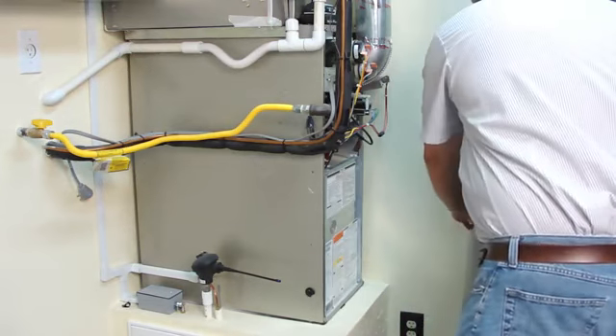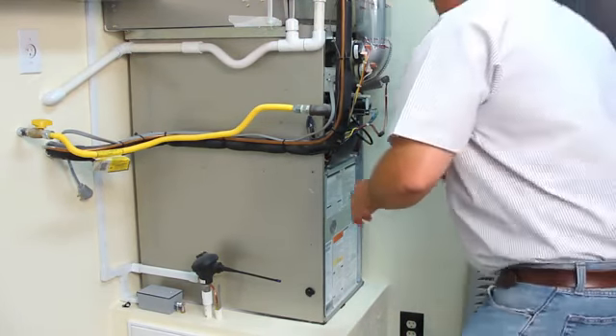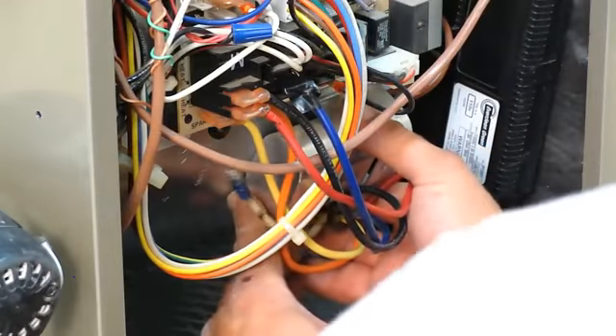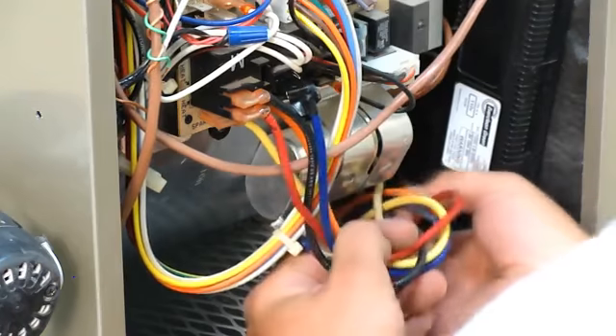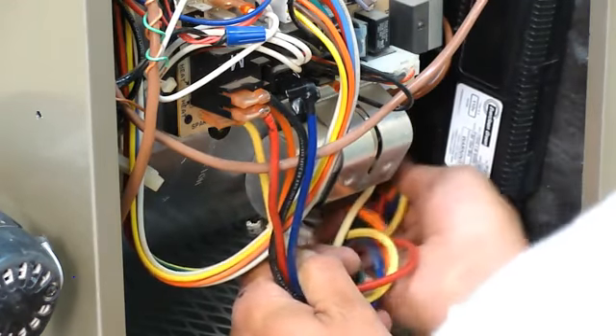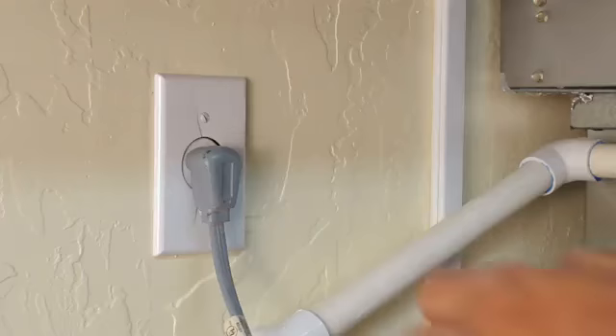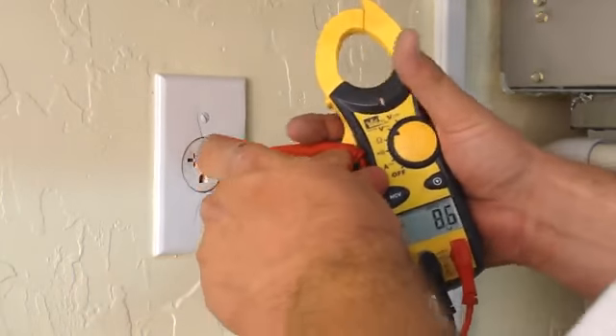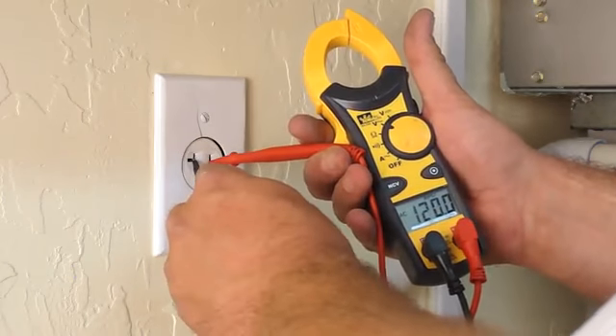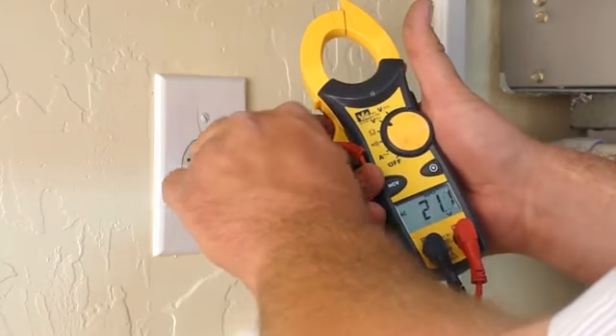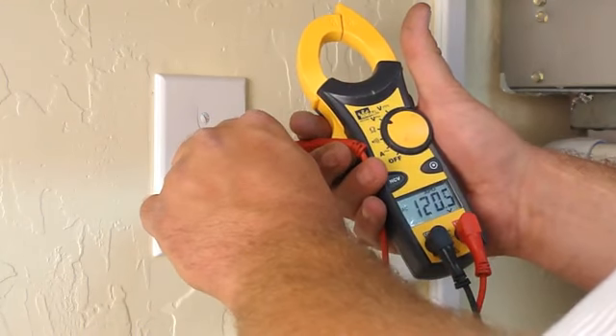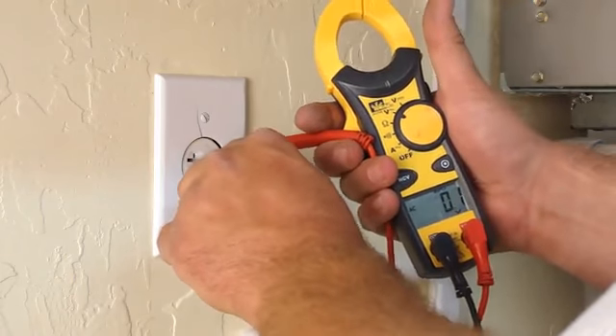To do this, check your HVAC unit for correct fan motor operation. It must be a permanent split capacitor or PSC single-phase 120 to 240 volt motor, and the motor and HVAC unit must be grounded properly. Next, you must verify the voltage. For 120 volt systems, perform the following checks: L1 to neutral, 120 volts. L1 to ground, 120 volts. Neutral to ground, 0 volts.